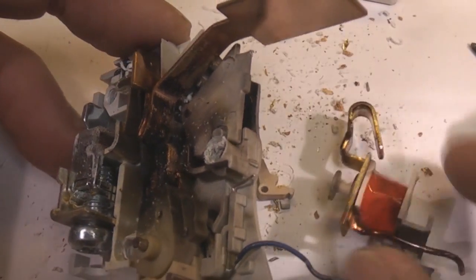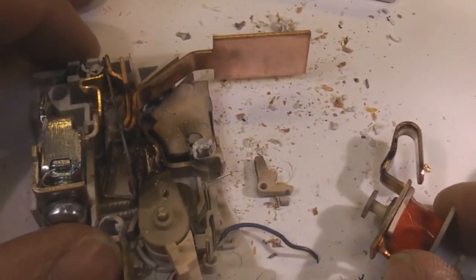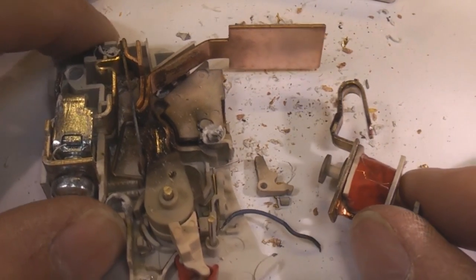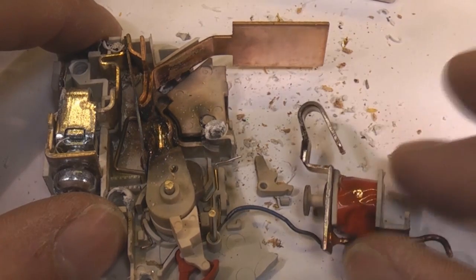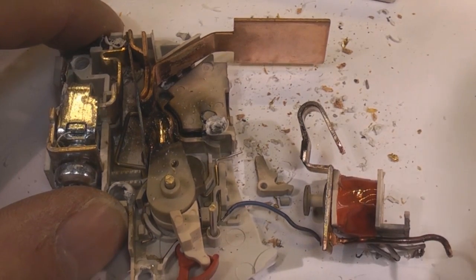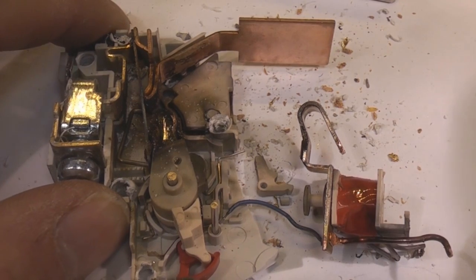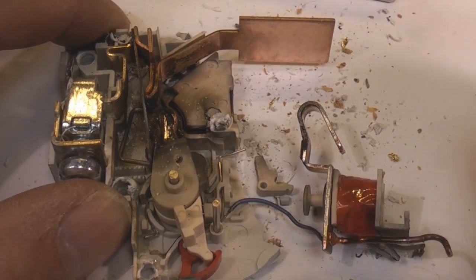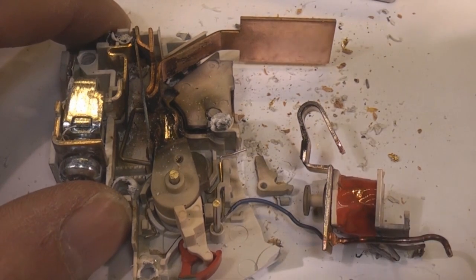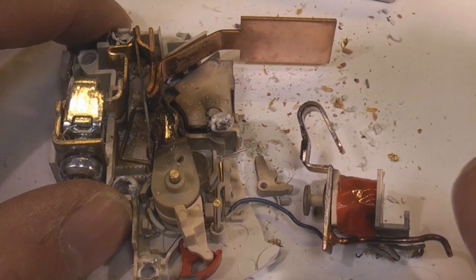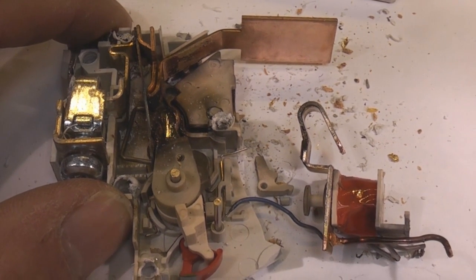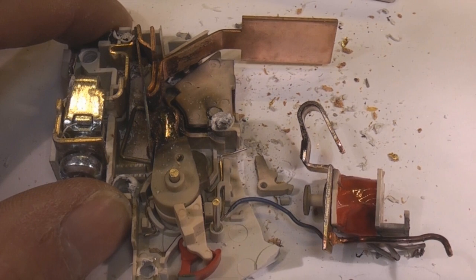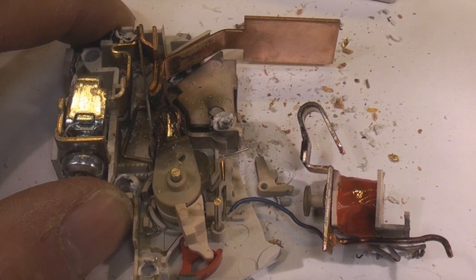happening. Now, of course, this probably isn't a scenario that these are designed to take, because the thing that causes all that destruction with the coil is the fact that it's coming from a very low inductance source, which means the rate of rise of current is very high, and that's what does all the damage. You know, the rate of change of current is what creates this moving magnetic field that causes all the destruction. And obviously in a conventional situation you'd have much longer feed cables, even though the actual supply impedance might be quite low. The inductance would be high enough that the rate of rise of current wouldn't be enough to actually cause the coil to disintegrate like that.